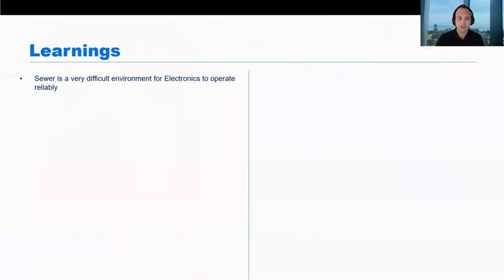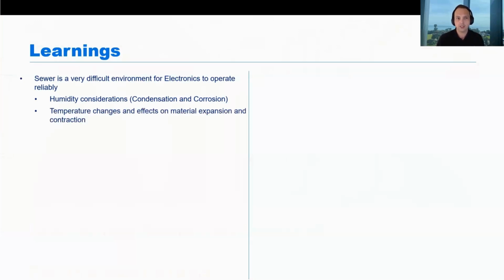So there's a lot of engineering on making sure that they operate reliably. It's a very, very harsh environment to operate in. There is a lot of humidity considerations. Condensation and corrosion were probably the top two issues that we had to deal with on the device's day-to-day operation. But there's also temperature changes and the effect on material expansion and contraction. So if you mix those three things together, it makes it really difficult for a device to operate in that environment. Then it's also the likelihood of explosive toxic gases in the operational environment, which make it very important to have that intrinsic safety certification.